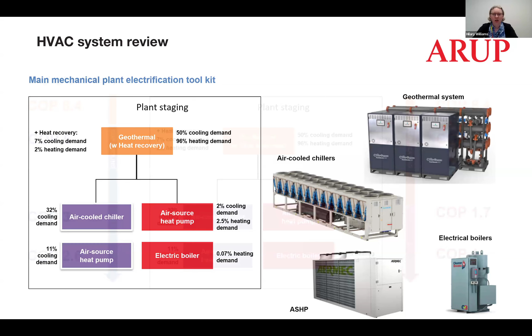And I think this slide very nicely highlights the differences and efficiencies that we are working with. The reason why we go with geothermal is it is the most efficient, and that's signified by this COP, a coefficient of performance. Basically, for every kilowatt of energy you put into the system, we're getting 8.4 kilowatts of energy benefit. That may seem like an implausible thing. Everyone knows that you can only be 100% efficient, but this isn't about creating energy, generating energy. It's about moving energy from one space to another.